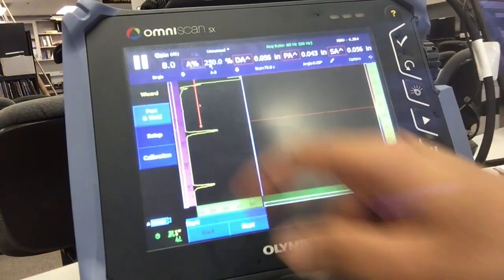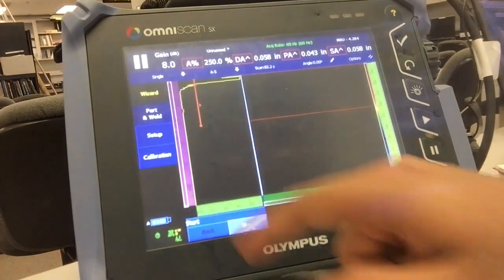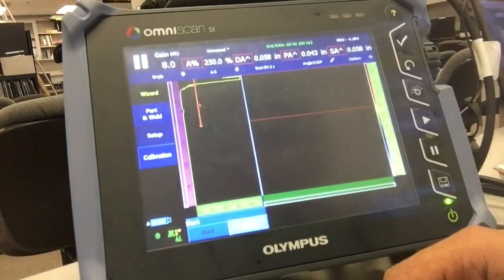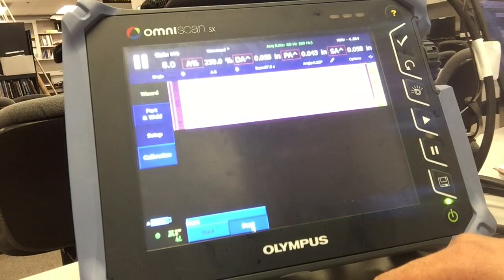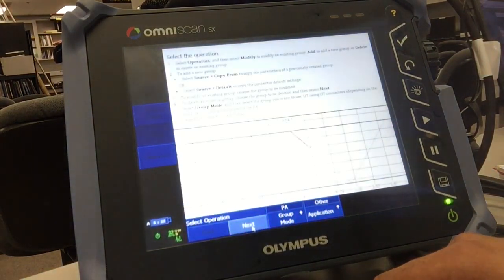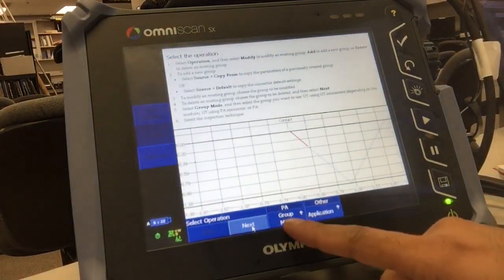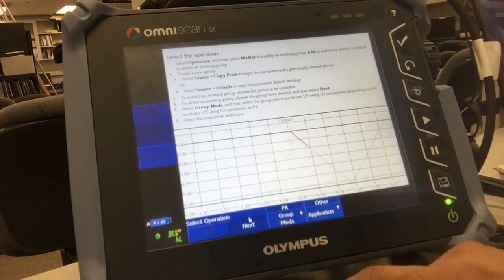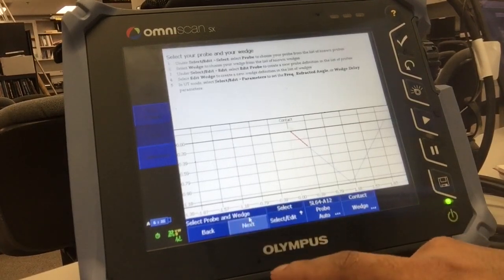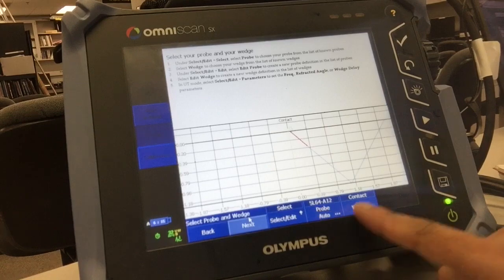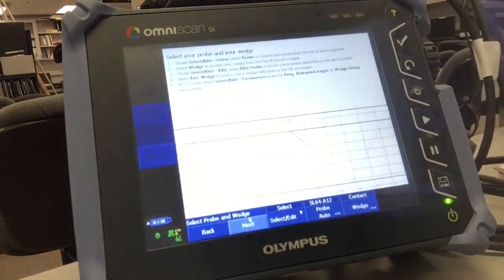So click on Wizard and directly go to Setup. Remember, this is a dead element check, so we're not really concerned about any part geometry. Phased array, application, other, click Next. Probe is auto-selected, and wedge we don't have any, so it stays on contact.